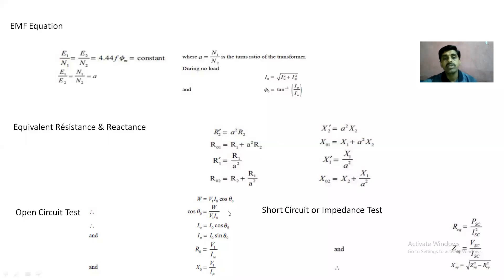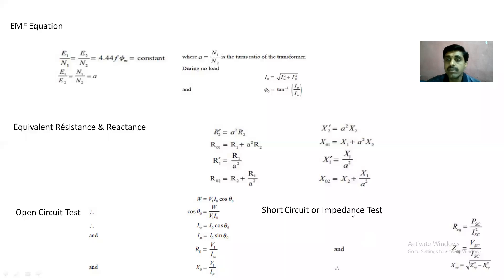From the open circuit test you can calculate R0 and X0. To calculate R0 and X0, we need the voltmeter, ammeter, and wattmeter readings. From those readings we can calculate cos φ0, then IW and Iμ, and from those we get R0 and X0. From the short circuit test you can calculate equivalent reactance and resistance. For that we need the wattmeter reading and the current. From that we can calculate R_eq, and Z_eq can be obtained by Vsc/Isc.